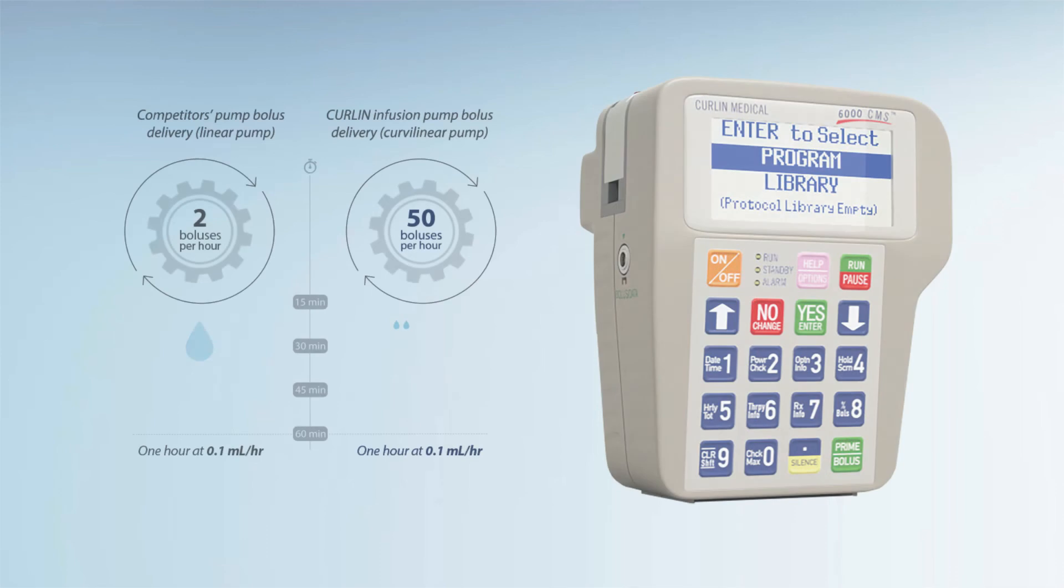Curlin ambulatory infusion pumps have been shown to deliver an extremely high resolution and continuity of flow, especially at low infusion rates. For example, at an infusion rate of 0.1 milliliter per hour, the Curlin pump delivers 50 micro-boluses per hour.